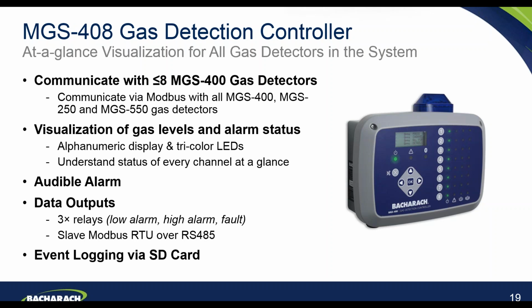The control panel can also be used as a slave Modbus over RS485. So again, if you prefer, you can have the gas detectors coming into this control panel, and then the control panel communicating and interfacing via Modbus into a third-party control system or a BMS. In addition, the 408 controller incorporates an SD card, which is used for logging events, so faults and alarms.